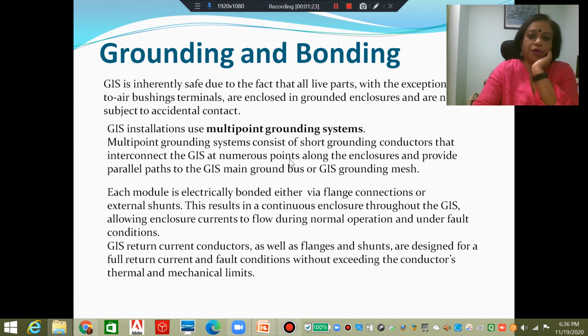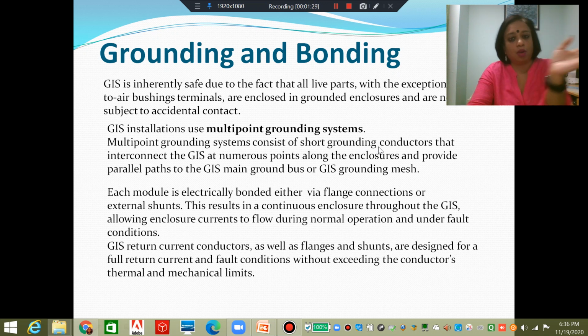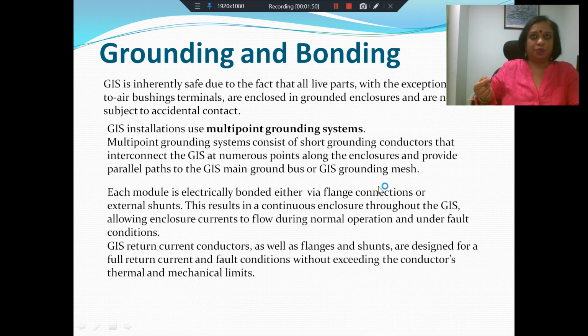So we use a multi-point grounding system. That means we have short grounding conductors through which the GIS is connected all along its route at multiple points. It is earthed individually. And of course, the entire enclosure is connected together. So these are all multiple paths to ground. These will provide parallel paths to the GIS main ground bus or the GIS grounding mesh. So you have multiple points of contact from the GIS enclosure to the GIS grounding mesh.